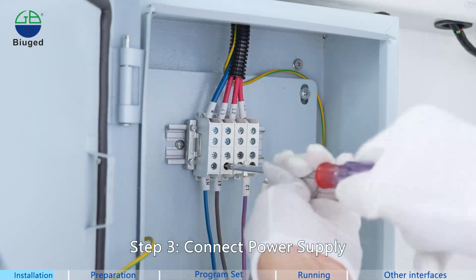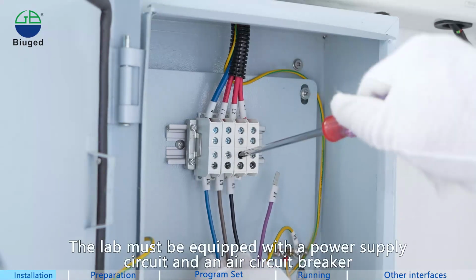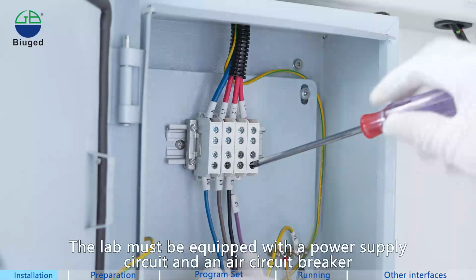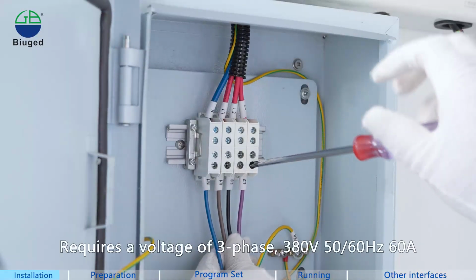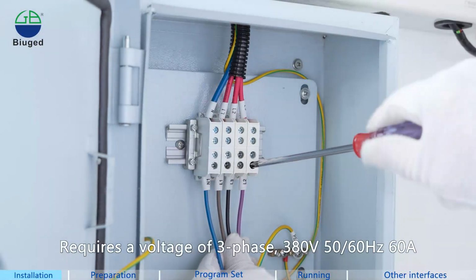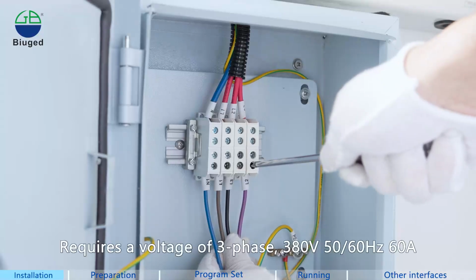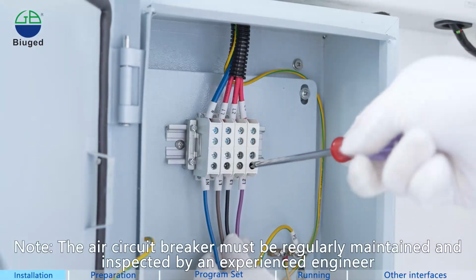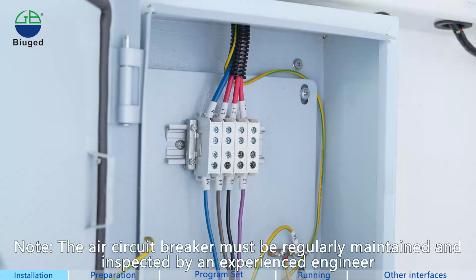Step 3. Connect power supply. The lab must be equipped with a power supply circuit and an air circuit breaker. Requires a voltage of 3-phase, 380 V 50/60 Hz 60A. Note, the air circuit breaker must be regularly maintained and inspected by an experienced engineer.